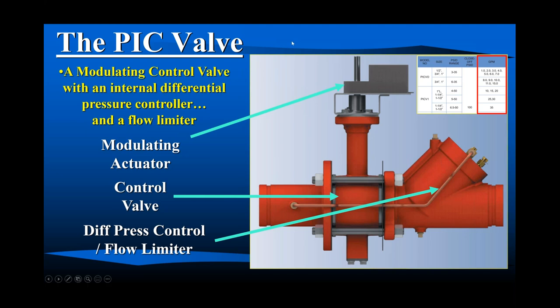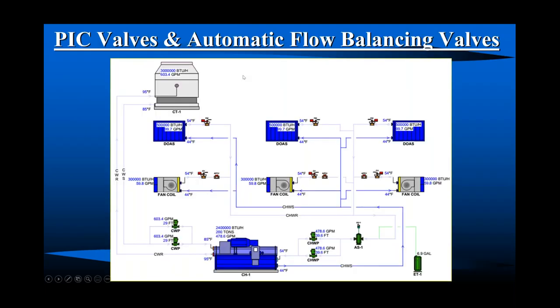Fabulous piece of equipment for modulating applications. Again, hospitals and the like, not for every application, but for those very dialed-in applications where a change in zone temperature cannot be tolerated. But it is a flow limiter. And the reason we bring it up is because it's being more and more applied, which is fine. But we have to know that it is a flow limiter. And as we said before, we don't put manual in parallel with flow limiters.